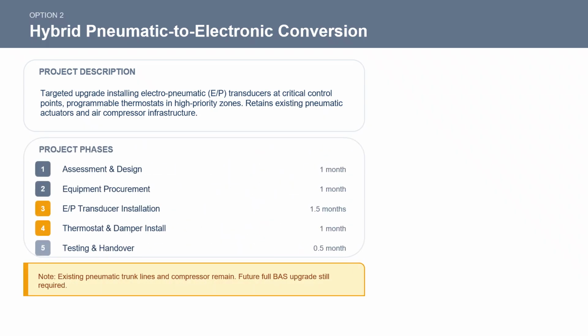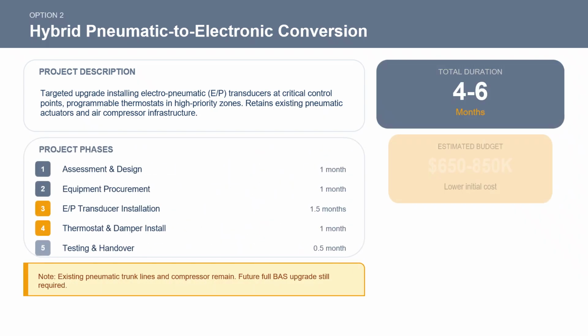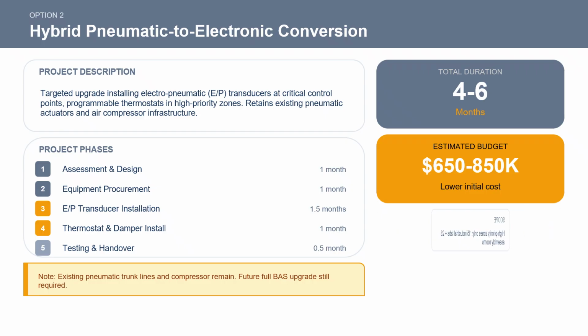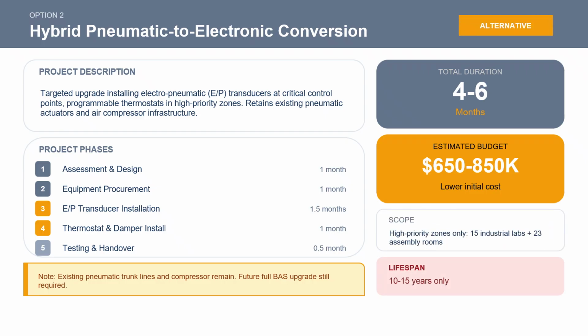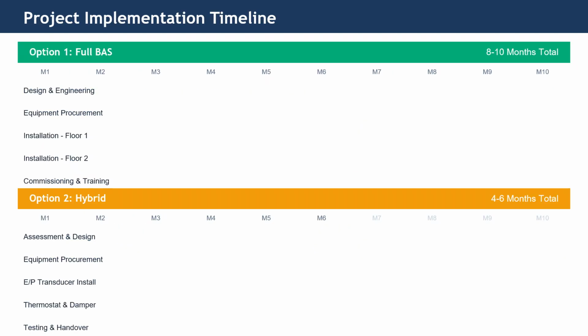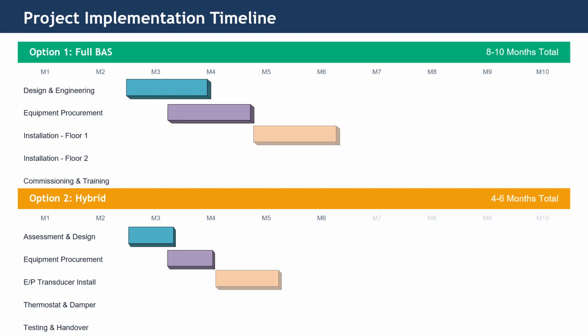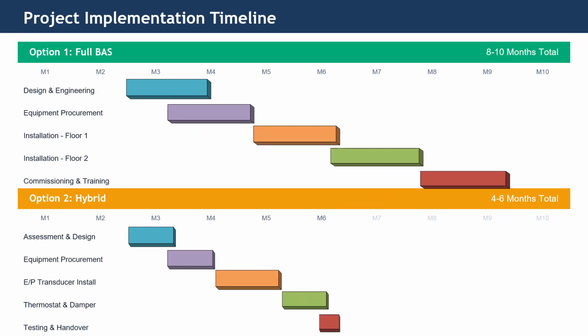Option 2 takes a different approach. It installs electro-pneumatic transducers at critical control points and programmable thermostats in high priority zones, but retains the existing pneumatic actuators and compressor infrastructure. The timeline shows a difference. Option 1 requires 8 to 10 months with phased floor-by-floor installation. Option 2 completes in 4 to 6 months. The hybrid is faster, but as we'll see, speed comes at a long-term cost.